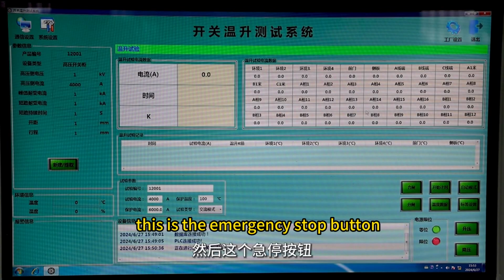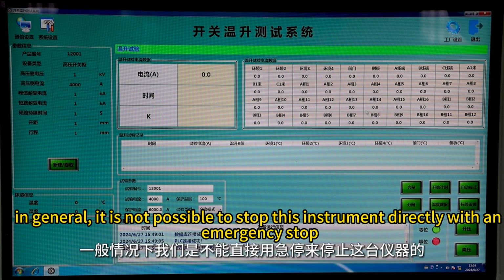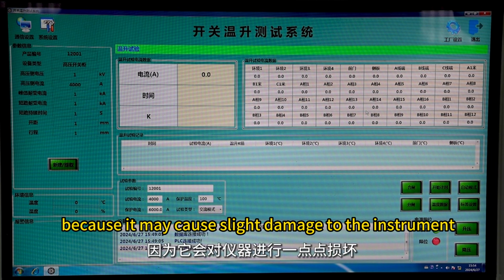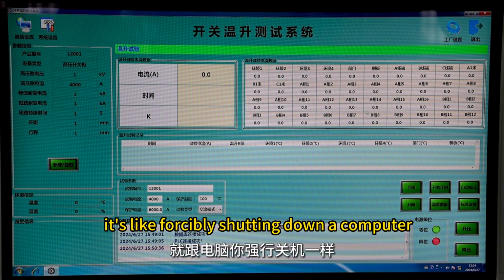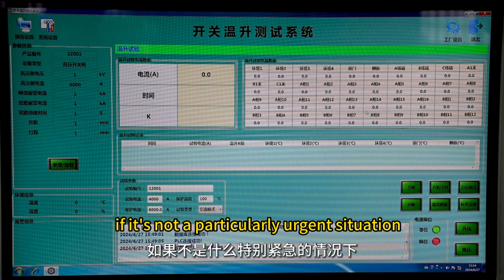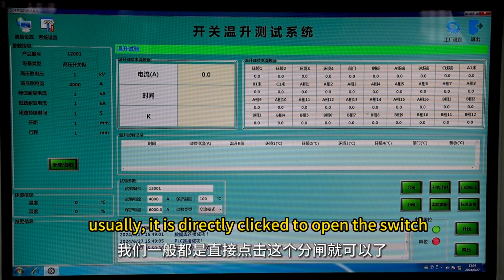This is the emergency stop button. In general, it is not possible to stop this instrument directly with an emergency stop, because it may cause slight damage to the instrument. It's like forcibly shutting down a computer. If it's not a particularly urgent situation, usually, it is directly clicked to open the switch.